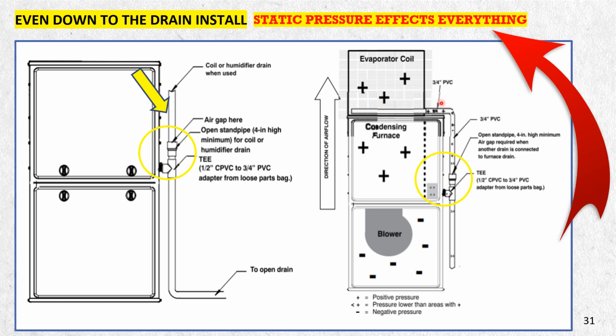Now, this coil is going to drain. Right now, this coil is at positive pressure. Positive pressure without air will not flow consistently. So you have to introduce air to that with either an open standpipe or an air gap around it, or if you came up here and put a T and this was left off, then it would flow. You just got to have air coming in where the two meet or before the two meet.